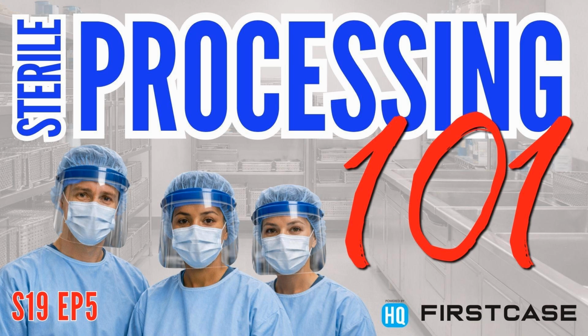And then there's not enough to go around to get the instruments sterile. Okay. Yeah, so you have to be a little pickier about that. Same reason with everything that goes in that low temp sterilizer, at least for hydrogen peroxide, has to be super duper dry because, again, that water gets in the way of the chemical sterilization process. So it works. It's very effective, but it's a little bit more dependent on the user getting it right.